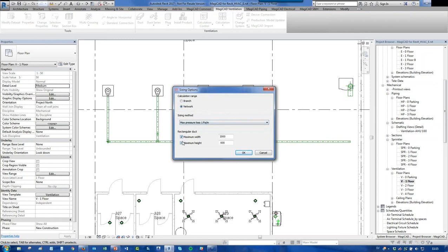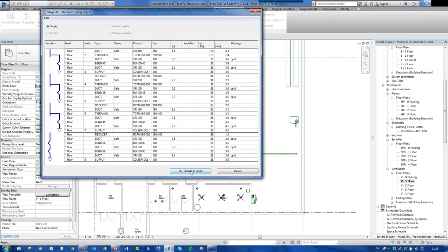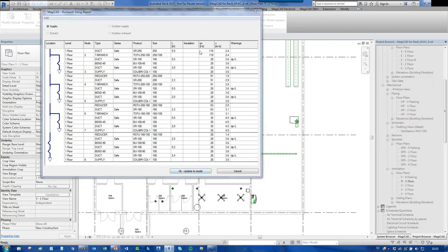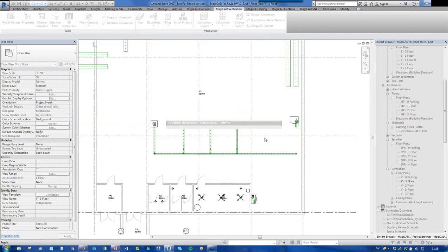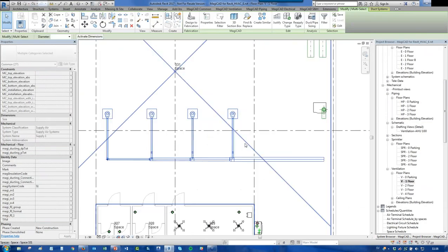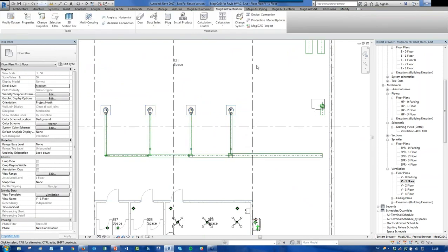If this is rectangular sizing we're doing, we can select some additional data, like max pressure drop of 1 PA per meter. Click OK, select duct, and I get a report of all the data I'd like to have. I can see I have 119 liters, and a length value, some addition, not so much data from the sizing itself, but okay. Then update to the model, and we have an updated model.